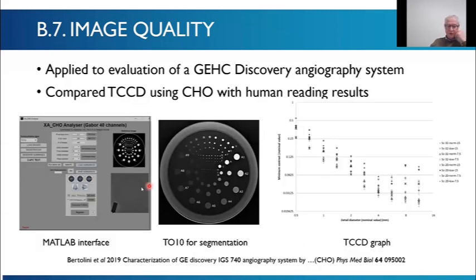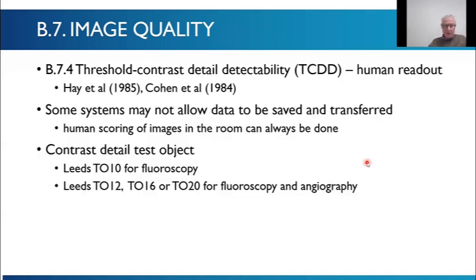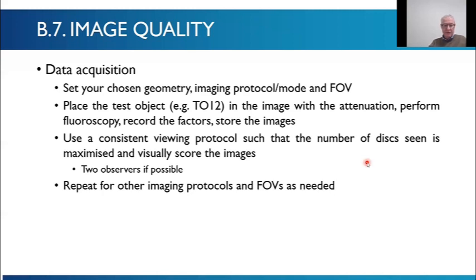And here's an example of Marco's method. So he has a CHO analyzer. This is TO10, I think. Then you segment these signals from here, and then you generate a contrast detail graph. Finally, you can do visual scoring, but I won't go into that because we don't have time. And also you can do a line pairs test object, so a sharpness test. And that can be done in the detector geometry or with a scattering material placed at the patient position, so you include some geometric unsharpness as well.